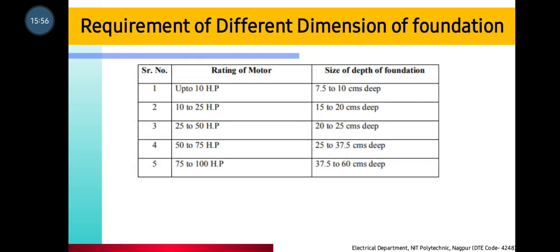These are the ratings of the motors and the size of the depth of the foundation. If the motor is up to 10 HP, then 7.5 to 10 cm deep foundation. 10 to 25 HP, then 15 to 20 cm deep. 25 to 50 HP, then 20 to 25 cm deep. 50 to 75 HP, then 25 to 37.5 cm deep. And 75 to 100 HP motor, then 37.5 to 60 cm deep.